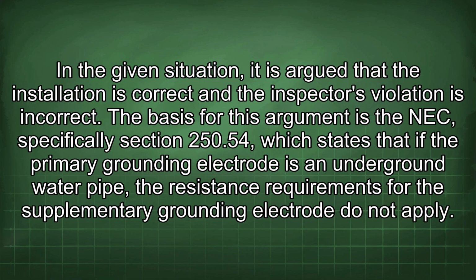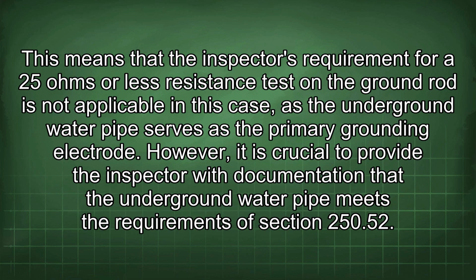In a given situation, it is argued that the installation is correct and the inspector's violation is incorrect. The basis for this argument is the NEC, specifically section 250.54, which states that if the primary grounding electrode is an underground water pipe, the resistance requirements for the supplementary grounding electrode do not apply. This means that the inspector's requirement for a 25 ohms or less resistance test on the ground rod is not applicable in this case, as the underground water pipe serves as the primary grounding electrode.